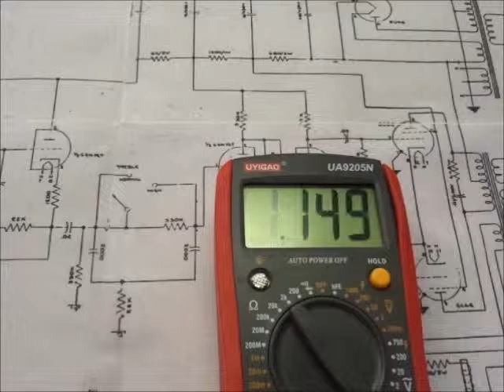Measuring over on the known good transformer between one plate lead and ground, I read infinite resistance, and measuring between the other plate lead and ground, also infinite resistance. So obviously we have a short between the iron core of the transformer and the primary coil.